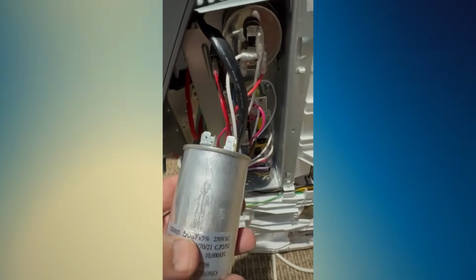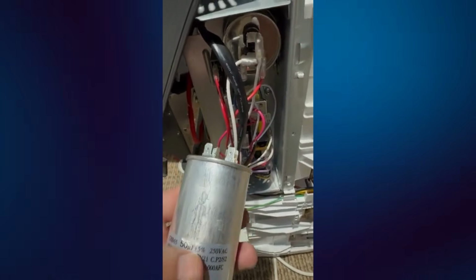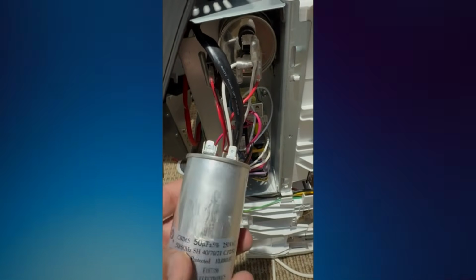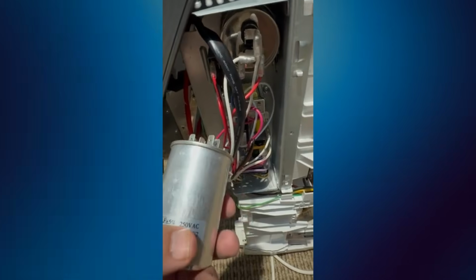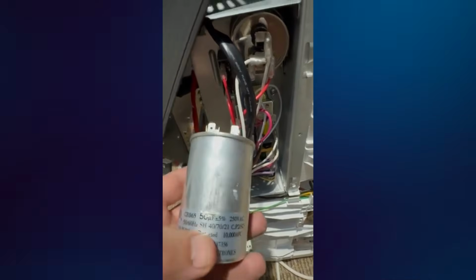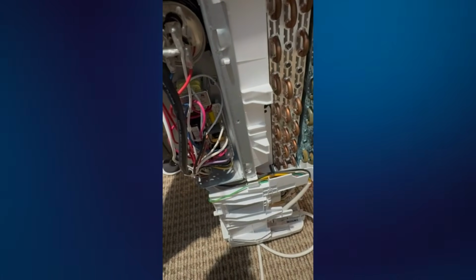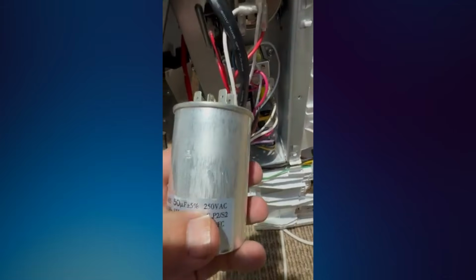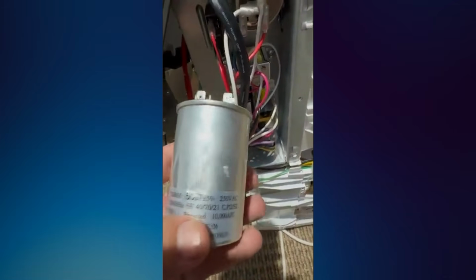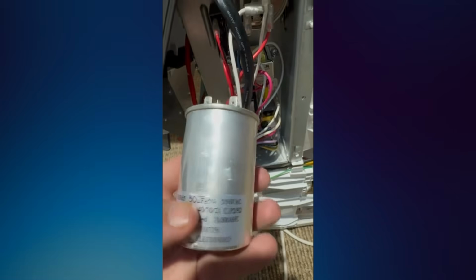A run capacitor must match the original capacitor's rating exactly. For example, if the original capacitor is marked 50 microfarads, the replacement must also be 50 microfarads. The voltage rating must never be lower than the original. A physically larger capacitor may sometimes fit, but electrical specifications, terminal type, temperature rating, and mounting must all be suitable.